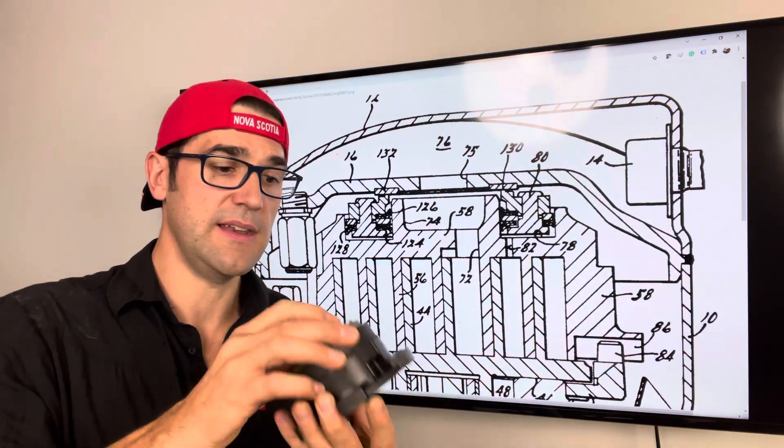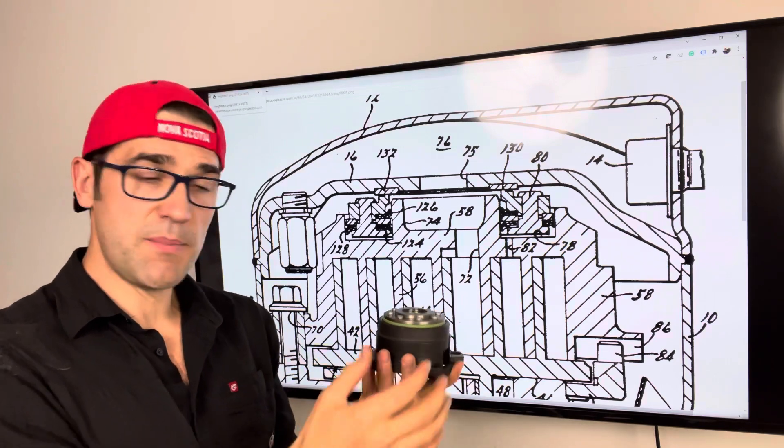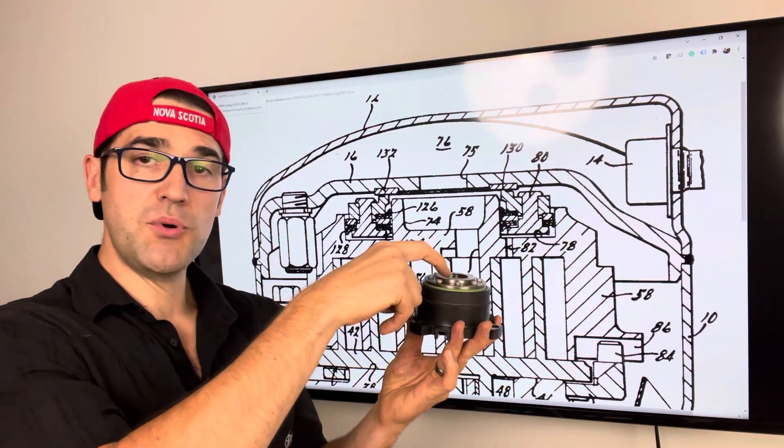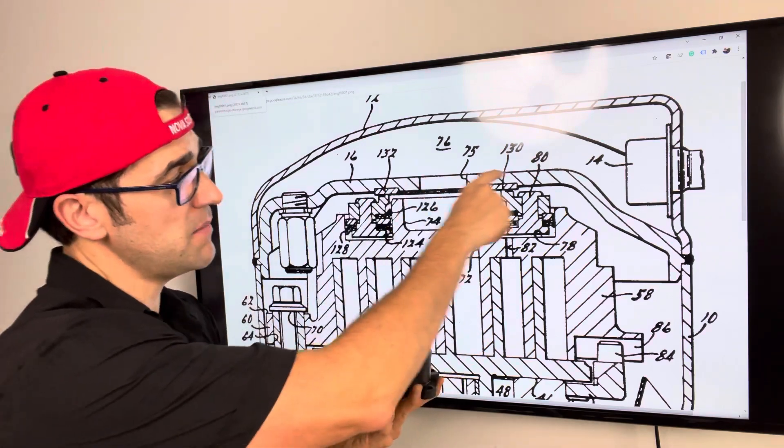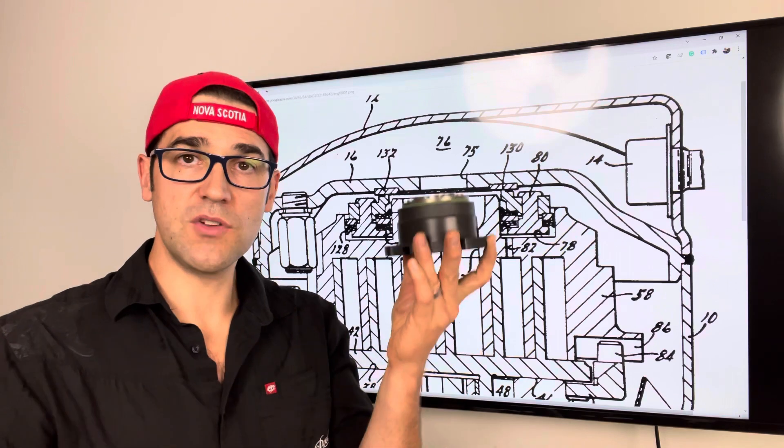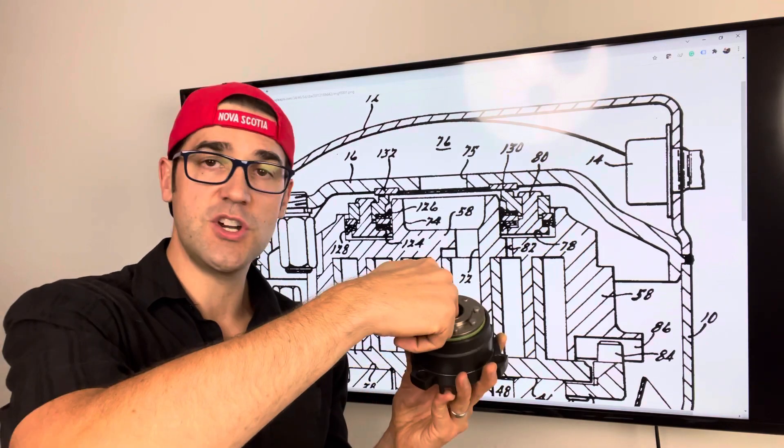As you can see there's a little hole drilled in there and that internal port comes here. As the compression starts up, pressure pushes up under there equally, pushes this floating seal up against the muffler plate. This is metal on metal but it's sealed by oil, so it pushes down and your orbiting scroll can pump and compress and discharge out here.